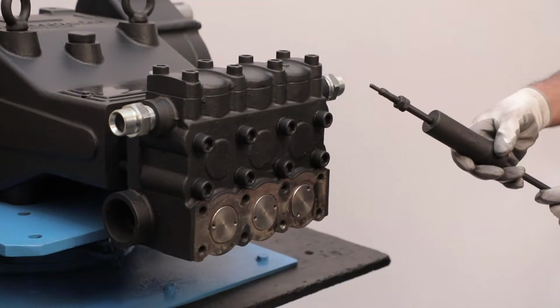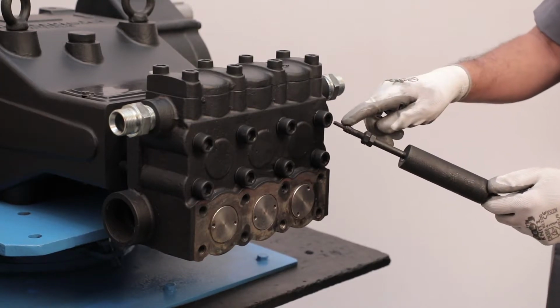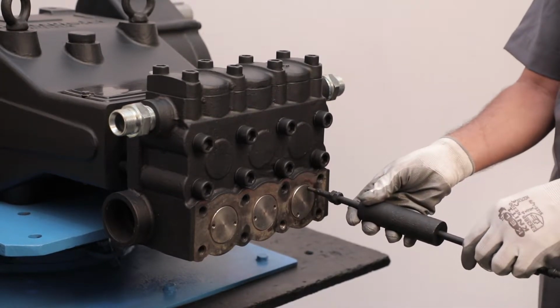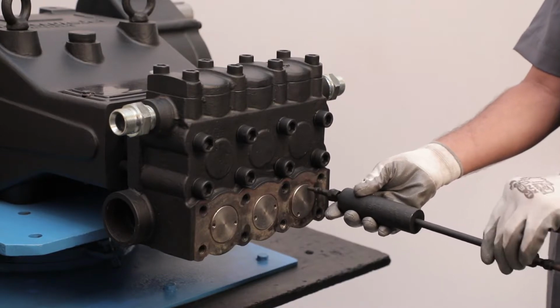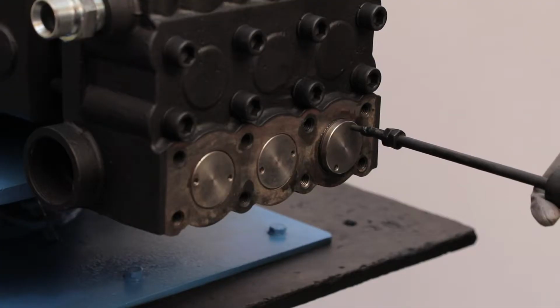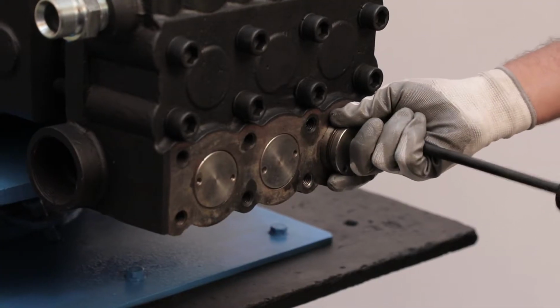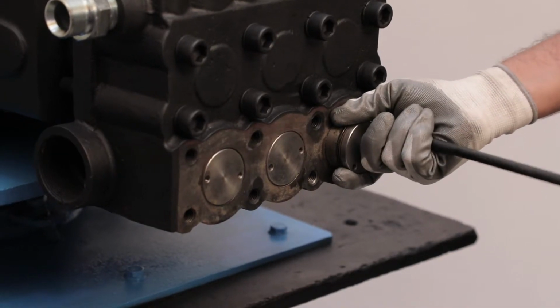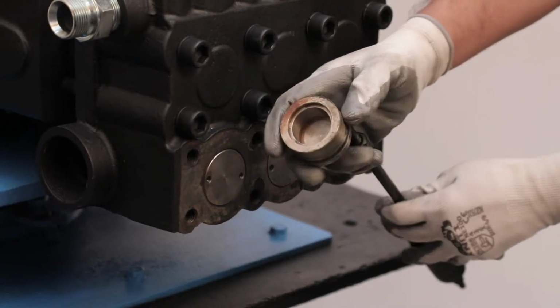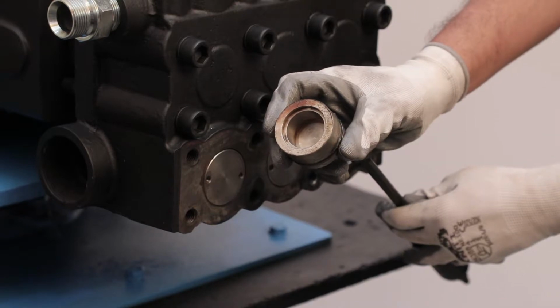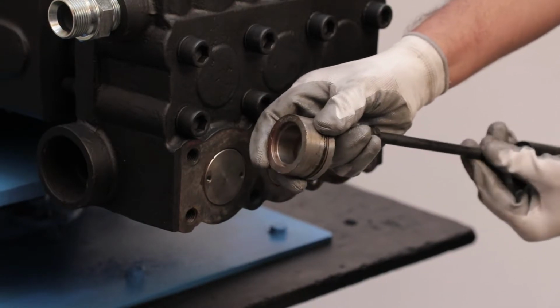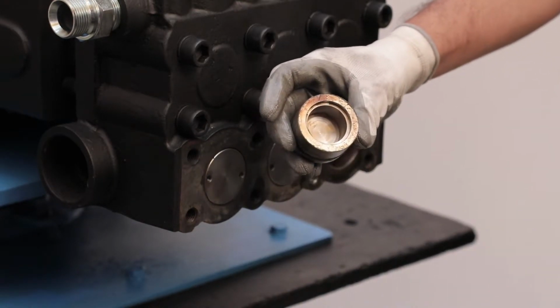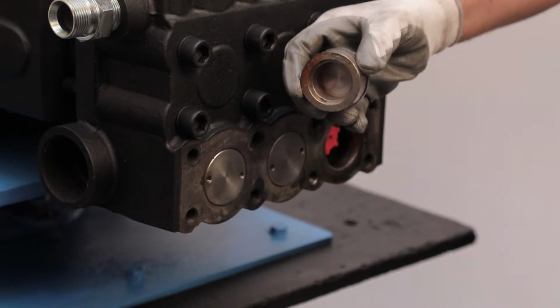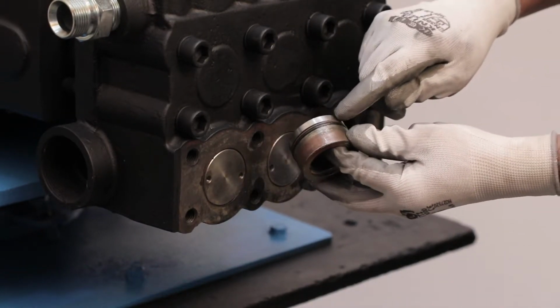After that, take valve puller and screw its threads into suction valve holder. Then, slide the weight of the valve puller, which pulls out the suction valve holder from the pump head. Unscrew valve puller from suction valve holder and place suction valve holder on a clear and flat surface.